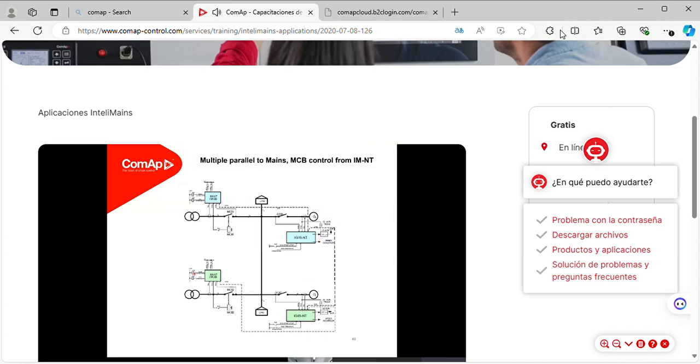And on your InteliMains MCB application, you are controlling the MCB1 and MCB2. You're taking the feedback, you're monitoring grid side current and voltage, and you're measuring the common bus voltage, which is created by the genset bus. And they talk to each other over the CAN bus or secondary CAN2 bus to share information. That's one typical example, which you already saw earlier in my explanation.